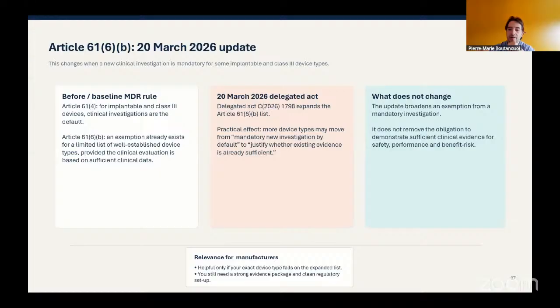But please note that this exemption from mandatory is not an exception to present clinical evidence. Even if your device is within the list, you still need to present clinical evidence, for example, from the literature, to satisfy the MDR requirement. And also, this update really helps you as a manufacturer only if your device exactly falls on the expanded list.